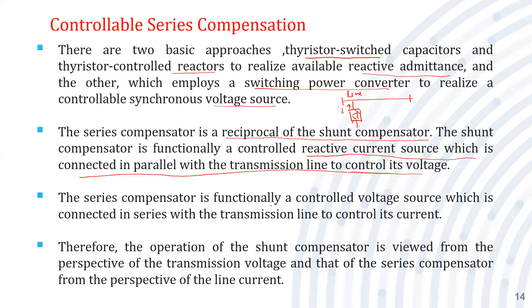For the series compensator, it is functionally a controlled voltage source, synchronized with the transmission line. The shunt compensator provides controlled reactive current, whereas the series compensator is a voltage source connected in series with the transmission line to control its current. The series compensator injects a variable voltage into the line.